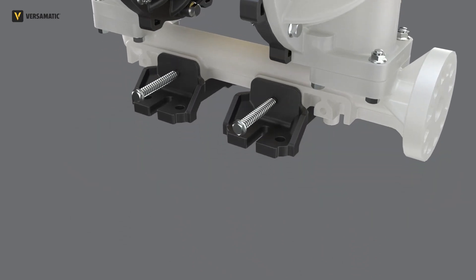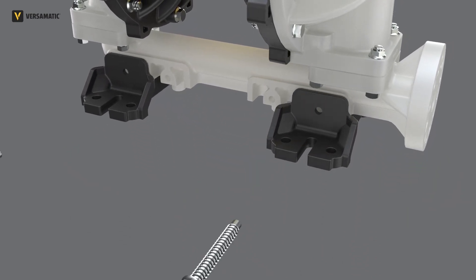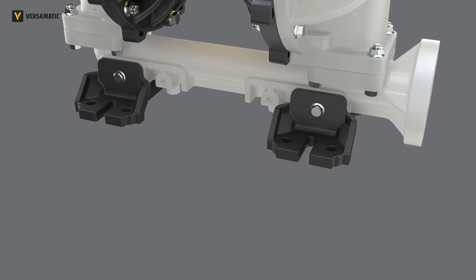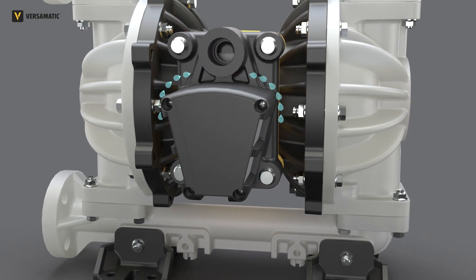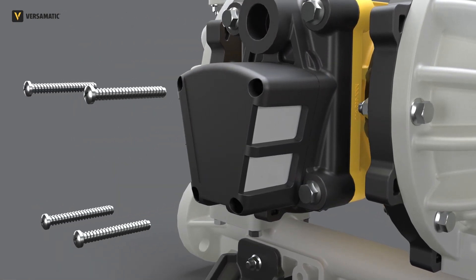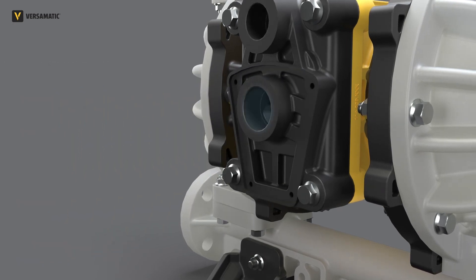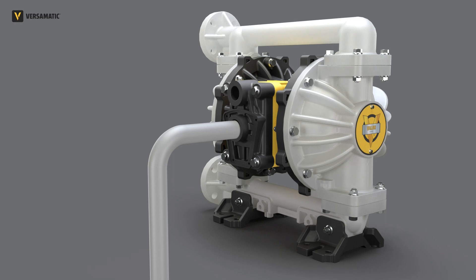The mounting feet are extremely versatile, fitting existing Versamatic pumps and multiple other manufacturer's dimensions. The muffler element is oversized and protected from the elements for better performance and less noise. The muffler cap and element can be removed to access a threaded port so the exhaust can be piped away for added safety.